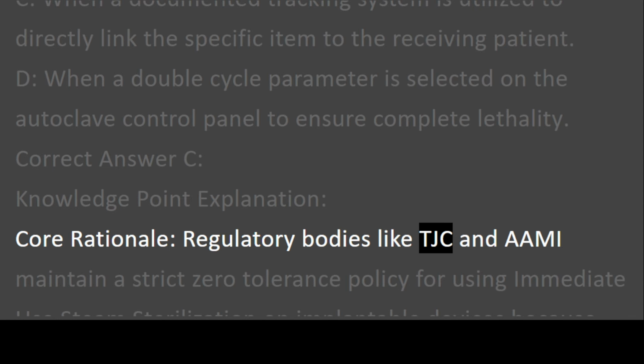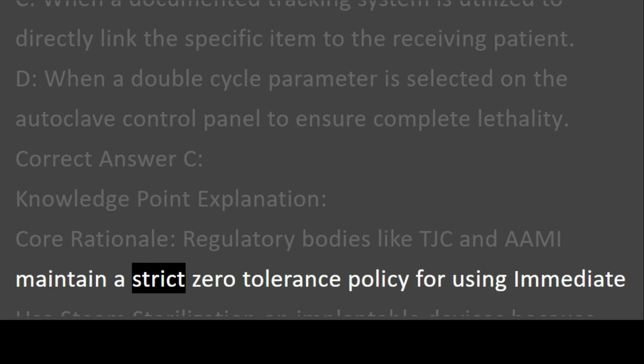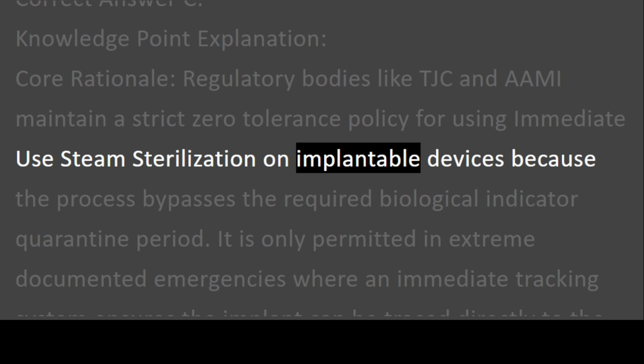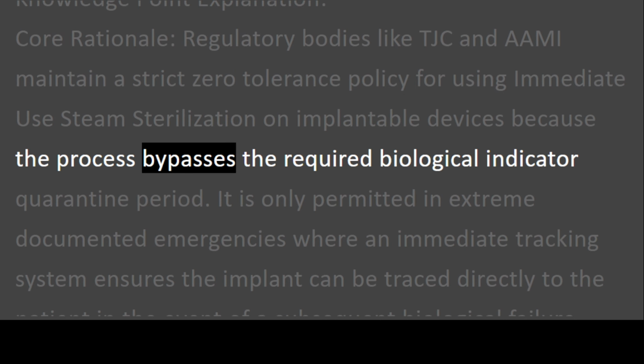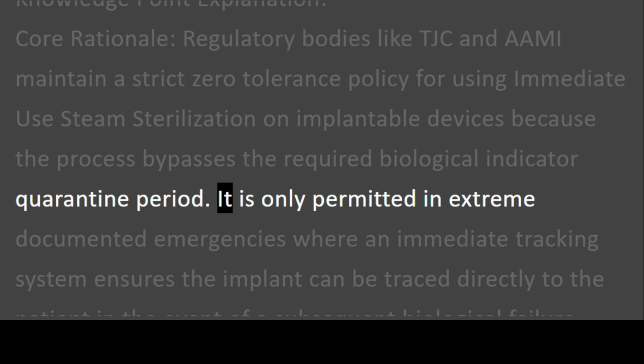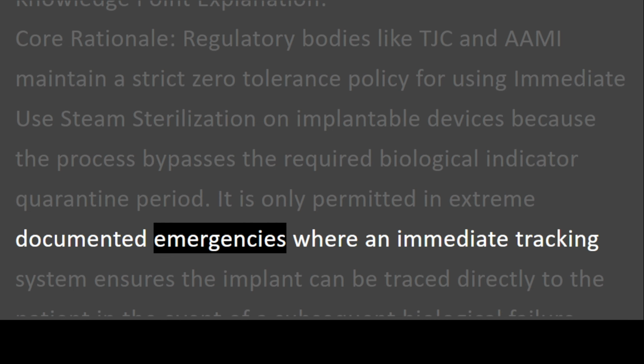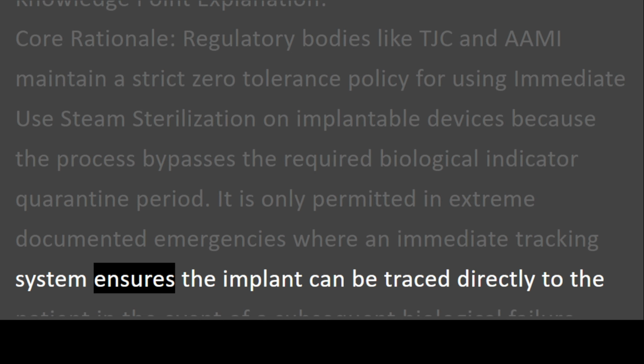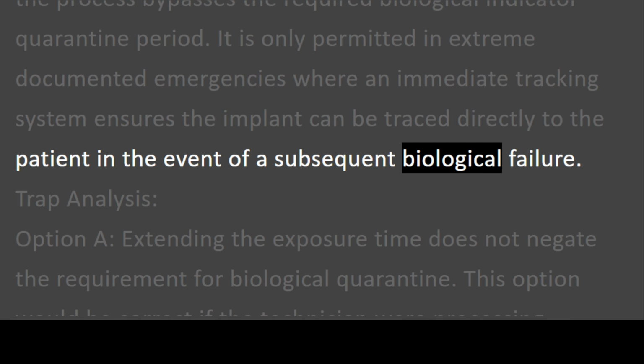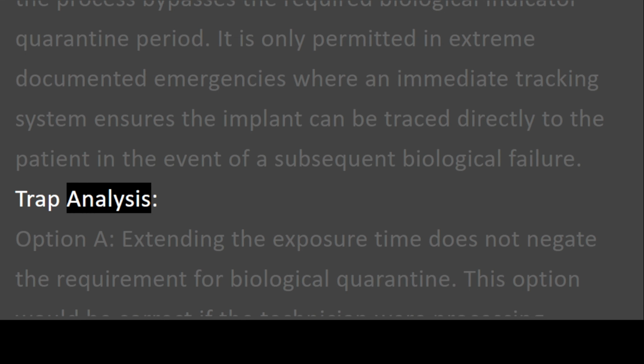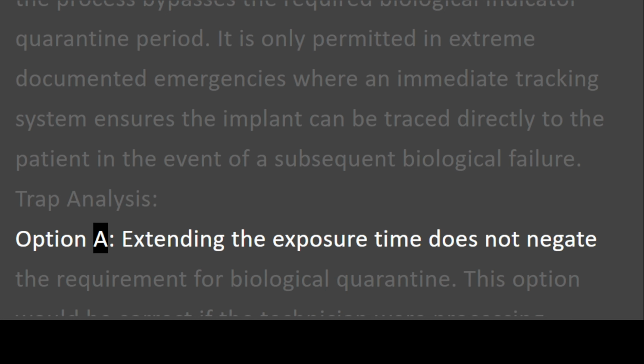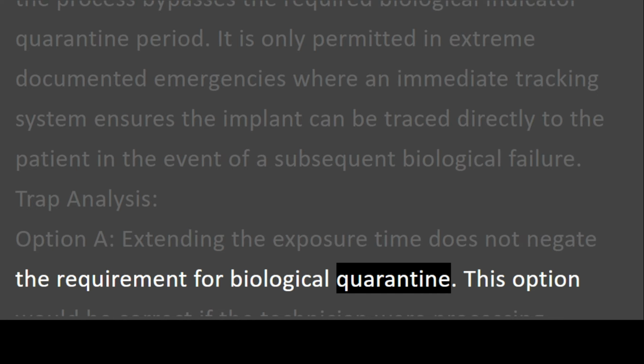Regulatory bodies like TJC and AAMI maintain a strict zero-tolerance policy for using immediate-use steam sterilization on implantable devices because the process bypasses the required biological indicator quarantine period. It is only permitted in extreme documented emergencies where an immediate tracking system ensures the implant can be traced directly to the patient in the event of a subsequent biological failure. Trap analysis. Option A. Extending the exposure time does not negate the requirement for biological quarantine.